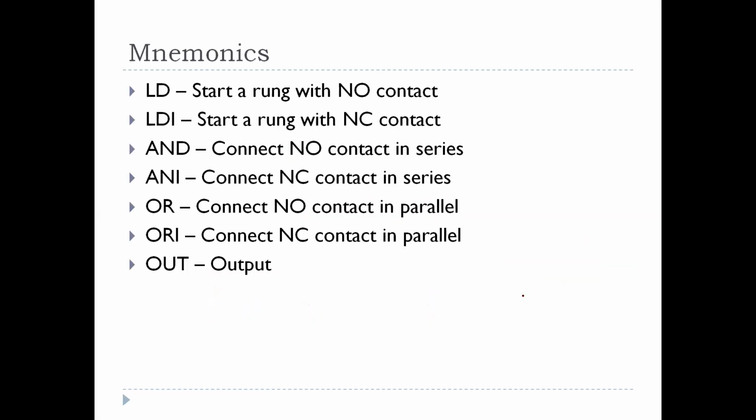The next method of programming is mnemonics. Mnemonics is an alternate programming language. It is a low-level instruction language consisting of a series of instructions with each instruction on a separate line. We'll see some of the instructions used. LD is used to start a rung with a normally open contact. LDI is used to start a rung with a normally closed contact.